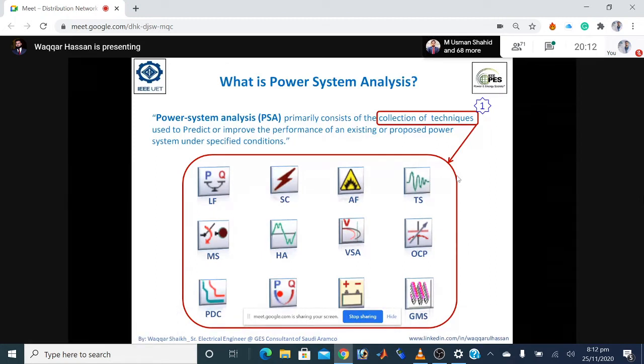Similarly, another important study, in the Middle East and in fact all over the world, is arc flash study, which is becoming a mandatory practice in every industry. Arc flash study is all about the safety of operators working in the substation environment. It tells us the possible incident energy levels in calories per centimeter squared, and what personal protective equipment operators should wear when working in front of energized equipment.